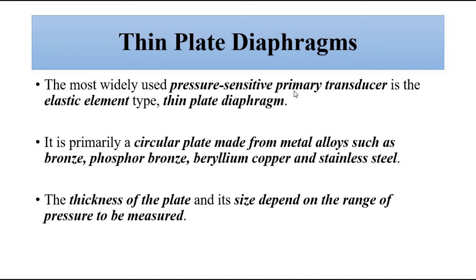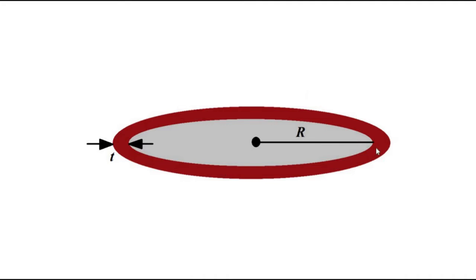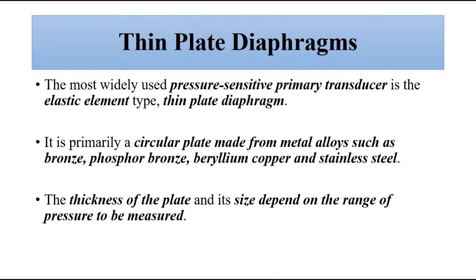The thin plate diaphragm falls in the primary transducer category — it does not produce any electrical output; it only produces mechanical movement or displacement. It is an elastic type device. The basic design is circular, with a certain radius R and a certain thickness. They are made from metal alloys such as phosphor bronze, beryllium copper, stainless steel, and other suitable alloys, depending on how much pressure it will be subjected to and what environment it will be placed in.